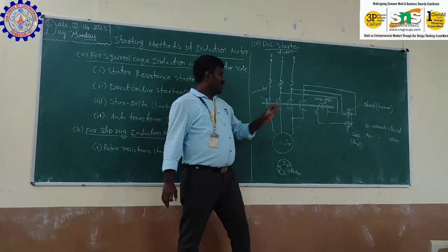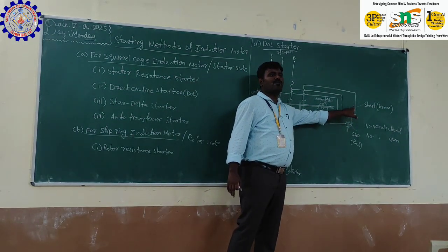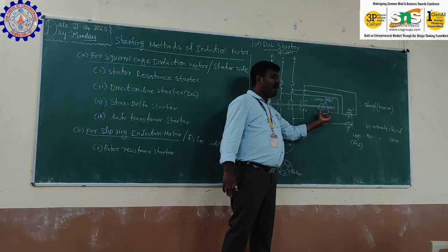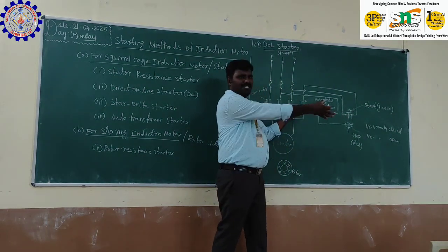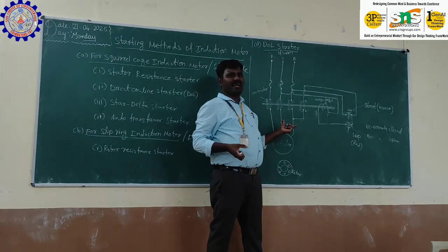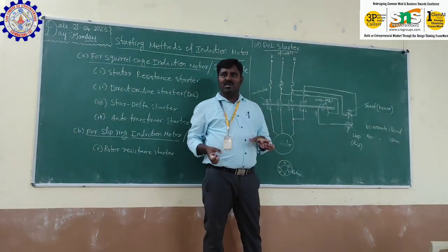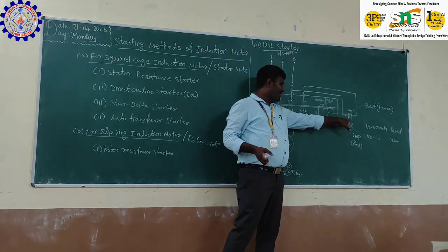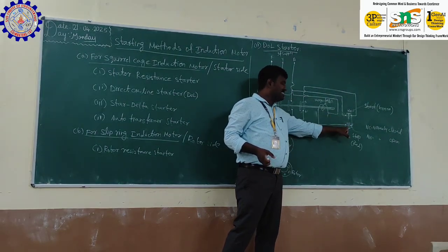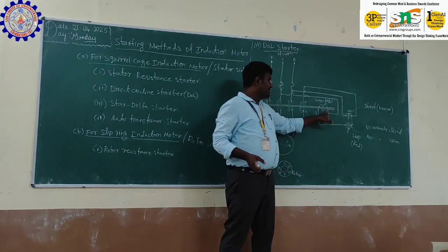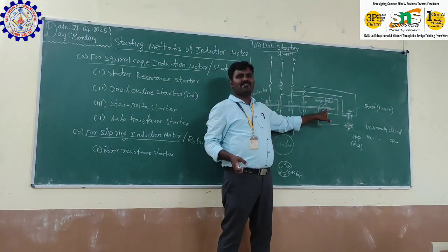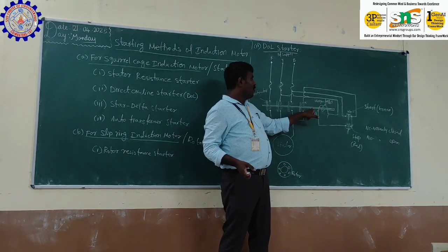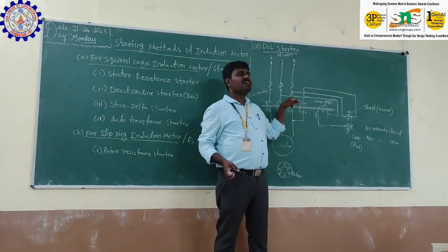Okay va? So if I want to start the motor, I want to push this green button, that is normally open. அப்படிங்கற பட்டனை புஷ் பண்ணிட்டோம்னா the coil is getting energization. இங்க இருக்க iron piece pull பண்ணி all the three phases will be connected, so the motor is get started. If I want to stop the motor, I want to push this normally closed button. If I am pushing this, magnetizing coil is disconnected from the power supply, so it's getting demagnetization. So because of this demagnetization, it not having the sufficient amount of magnetic power to hold the iron piece, so it will be released to the initial position.